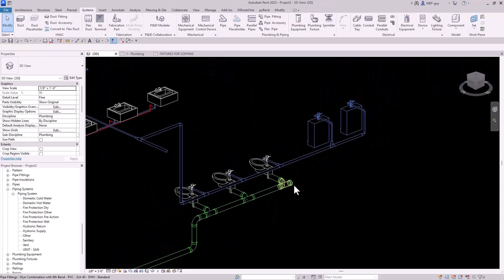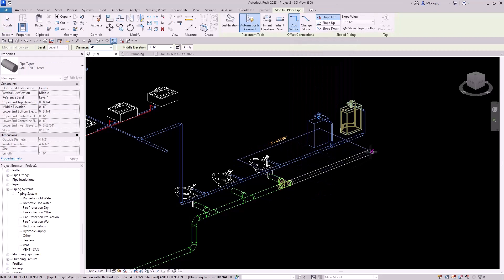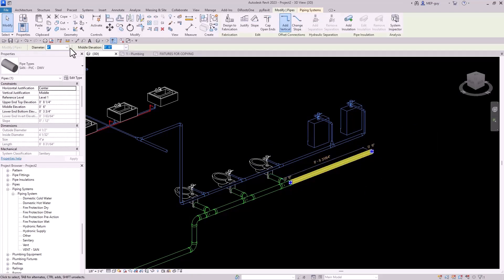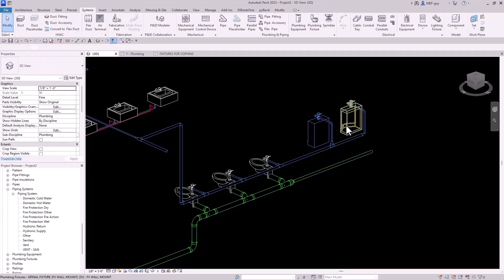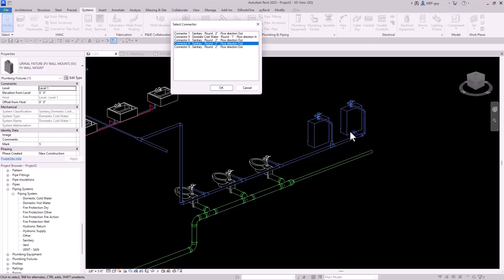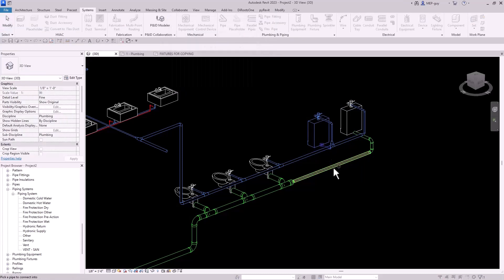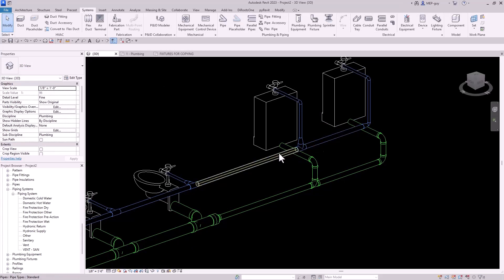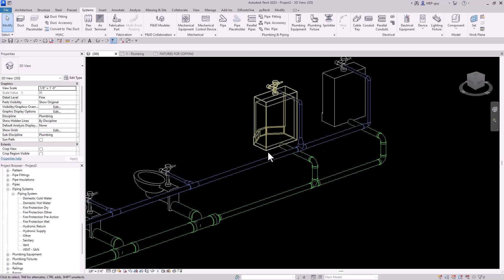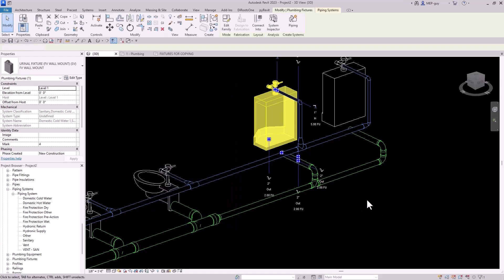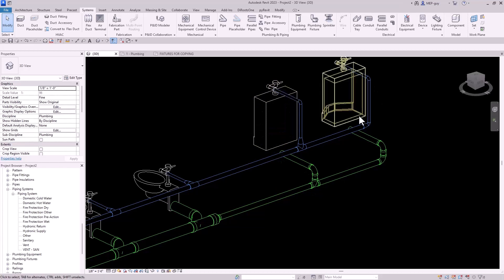We're going to hit plus, keep drawing pipe — right click, draw pipe, hold shift. When I get to the right spot, Revit will highlight my fixture. Now we can reduce the size to two inches and use our connect into command. We'll click the sanitary connector coming out of the bottom and adjust the height later. Do the same thing — connect into, use this sanitary connector, and that looks great. Now if we had an intersection between our water piping and needed to bring the sanitary piping down, we can do that with these custom fixtures. Go to edit type — I have a parameter called sanitary outlet height. If we need to move this down to maybe one foot two, we can click OK and that moves the sanitary piping down. They're very customizable.